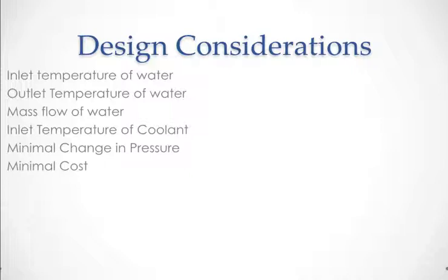For this project, the inlet temperature of water is 57 degrees Fahrenheit, and the outlet temperature needs to be less than or equal to 60 degrees Fahrenheit. The mass flow of the water was calculated using Newton's law of cooling. This was done using maximum daily thermal energy produced by MSU's HPC.